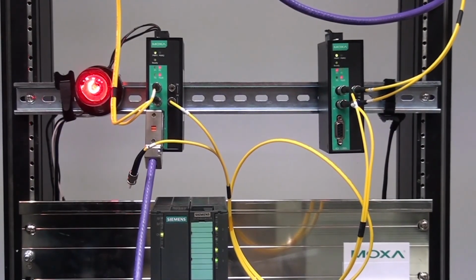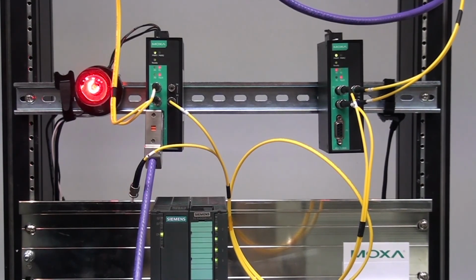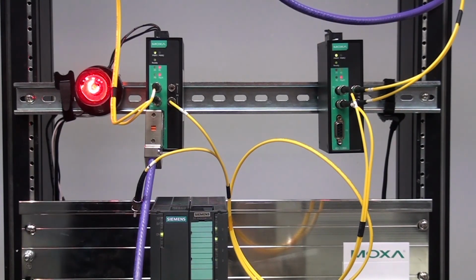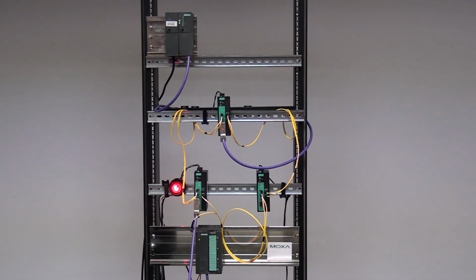Here, after we've disconnected the cable, we can see that all the LEDs on the Siemens PROFIBUS device indicate that the communications are still normal thanks to redundancy. All the Siemens LEDs are still green. However, the LEDs on all the converters in this network will now indicate to us that there is an issue. You can even hook up an external relay alarm to the converter so that any connection issue is visible from far away.